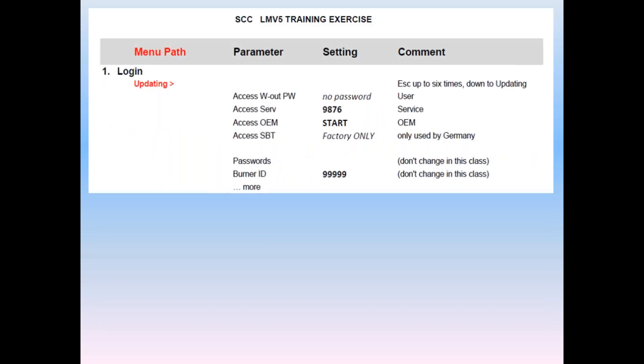Okay, let's begin the exercise. Whenever you get lost, simply escape up to six times and proceed through the menu path on the AZL. Here we will navigate up and down until we see updating. Once we get to updating, enter is pressed. We are prompted to choose a level. We will choose the OEM level. Enter the password, S-T-A-R-T. Do one letter, press enter one at a time until the entire password is complete. One final entry puts us into the menu. Any incorrect passwords will result in an error and you can try again. Once you're logged in, the password is valid for two hours after you stop pressing any key. That's the factory default time and can be adjusted as you see fit. The parameter is called password time. In this section of the menu, you can change the passwords and edit the burner ID.